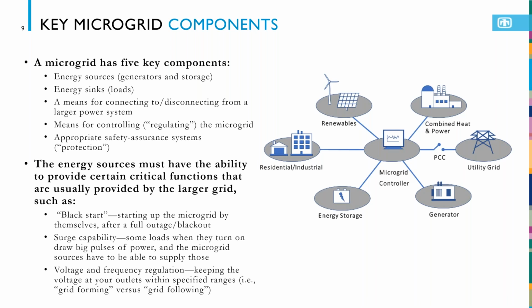It also needs to have a black start capability. When the grid goes out, and let's say the microgrid goes out, you have to find a means to start it off. A lot of times this is missed, I think, because you're trying to start an inverter or a generator. You need the brains. You need power to the brains. Sometimes you have a UPS to power that controller, so you can figure out how to start things. So that's a big thing. Some type of backup power to make sure the brains of the system, the controller, is operating properly. And then once you get that going, typically it's a generator that's started, usually one of the big sources, then maybe followed by an energy storage, and then followed by some loads. So a very coordinated approach to starting off a microgrid.